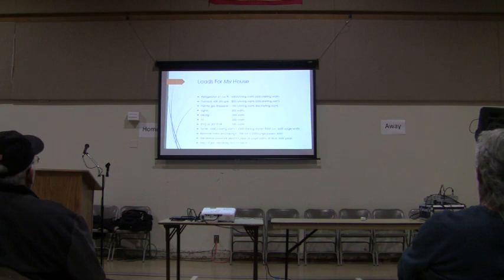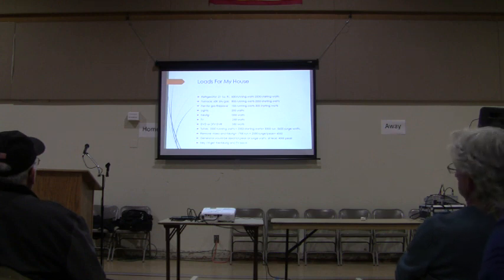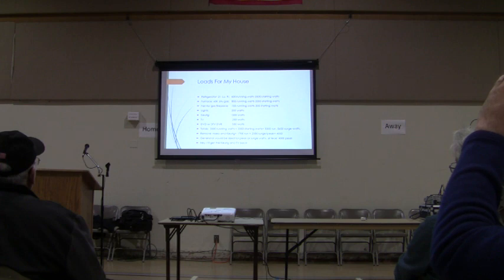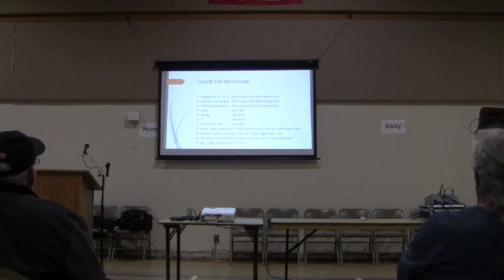So here's my house: a little 1,400 square foot 1974 special, no insulation, cut-off A-frame, crappiest house on the block that I got at a fire sale and spent a year and a half rehabbing before I moved in. These are the loads I'd have: a refrigerator, 21 cubic feet, 600 running watts, 2,200 starting watts. I have a 60,000 BTU gas furnace with about a half horsepower blower motor, 800 running watts, 2,300 starting watts.